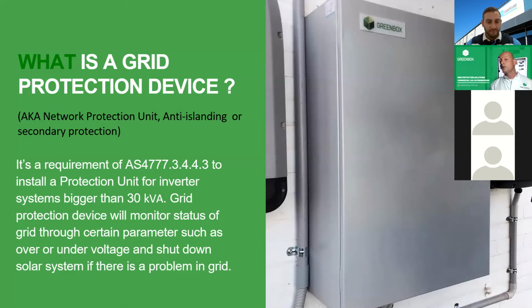Anything that is required when the grid is out of phase covers 5 things, of course: your under voltage, your over voltage, your under frequency, over frequency, and your rate of frequency change. If any of those items fall outside of the DNSP network settings, it will then shut down either one or all of your inverters at the same time.